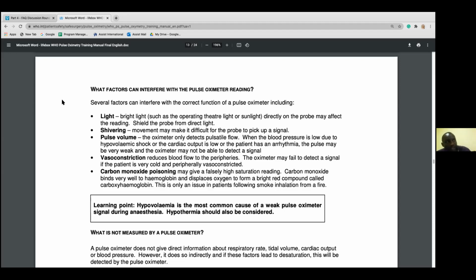The other thing is that you need to make sure that you get the correct size of the pulse oximeter probe, because if you are not using an appropriate size, that may also have a tendency of interfering with the accuracy of the reading. So make sure that you identify the correct size, whether it's pediatric or adult size. And then inappropriate placement also. You need to make sure that you orient the probe in such a manner that it fits appropriately on your finger and not the other way around. And normally our probes will have a clear indication or sign on the probe that will help you know which orientation to place your pulse oximeter probe. So ensure that you place it correctly.